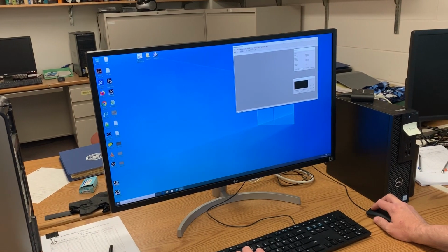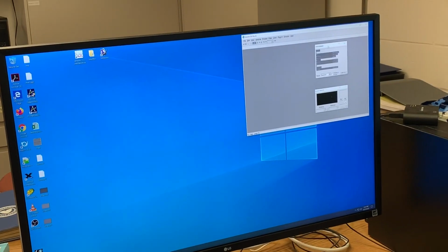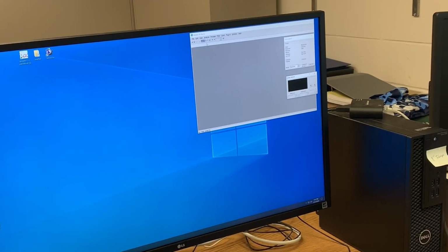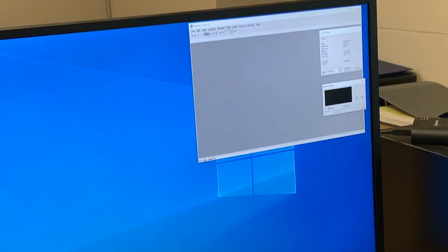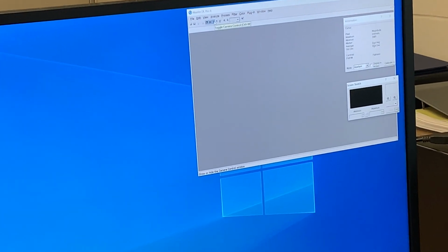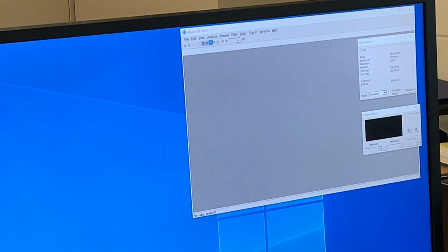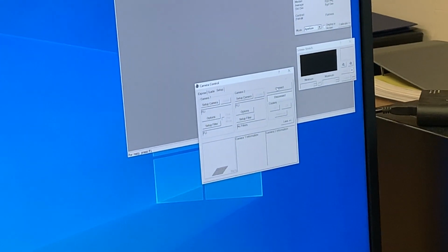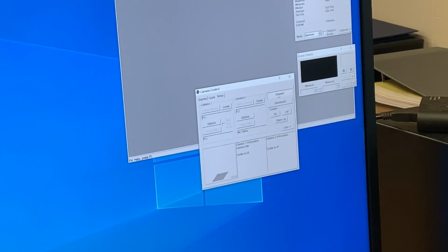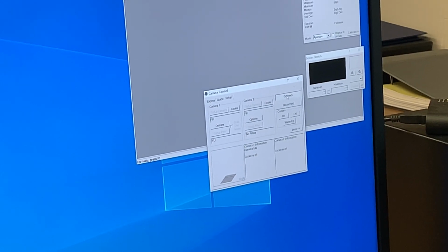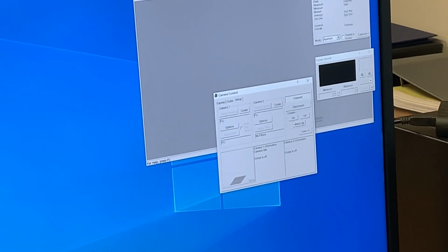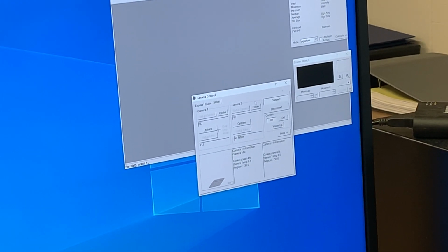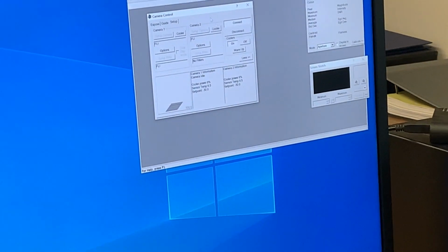And this is going to bring up our control panel for the CCD camera. Up here there's a little button, there are two that represent these two, and a third one right beside it that we're going to click on. That will bring up our CCD control window. What we're going to do now is connect to the camera by hitting connect. Then come down here where it says cooler on, and we're going to turn on the cooling system.